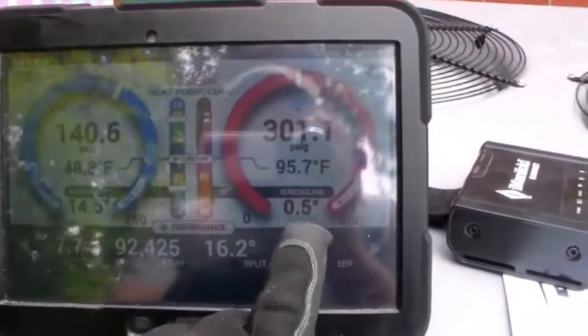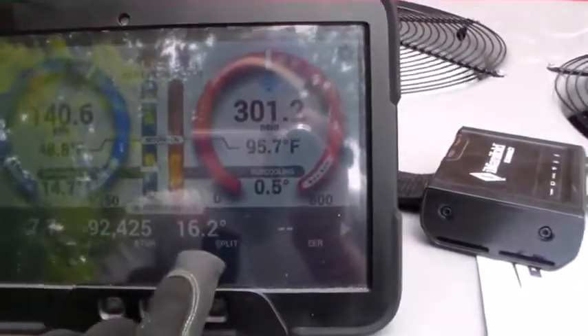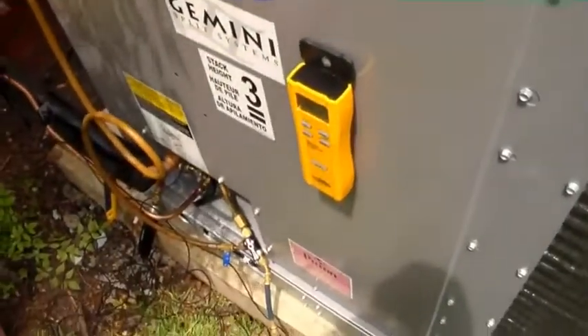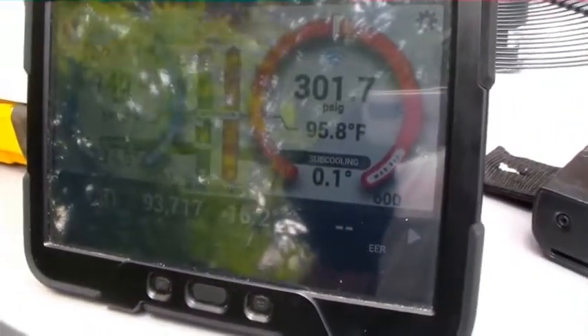We have a good superheat and very little subcooling. Going by the equipment charging chart I have here, which ensures we have some subcooling, we are still lacking charge a little bit, so we're going to keep on charging it up. It's definitely humid inside, so our target temperature split was lower. It's starting to climb back up a little—if you can see it down there at the bottom, 16.2. Our original target was 14, but we've humidified the air quite a bit.